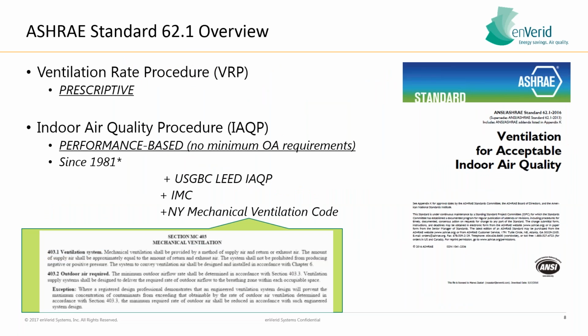Just a little bit about ASHRAE 62.1. For those who are not familiar, ASHRAE 62.1 essentially has two sections to calculate how much outside air is required for buildings. One is the ventilation rate procedure, which is what most of us are familiar with, which is a prescriptive methodology for figuring out how much outside air to bring into a building to remove contaminants that are emitted within the space. So off-gassing from furniture or CO2 emissions from individuals, and using outside air to essentially flush out that air.